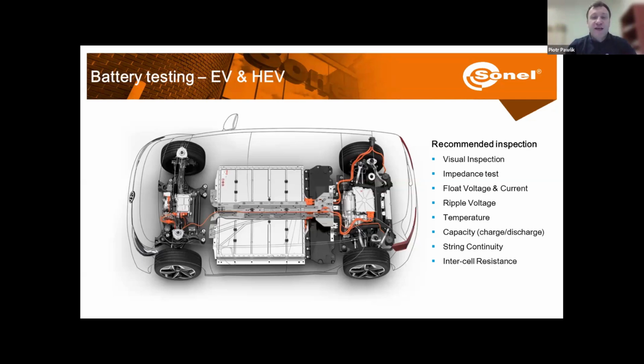But as the battery is aging, they just don't tend to keep the level of their voltages and currents. So they may fluctuate and they will have the AC component. So for that reason, we are checking impedance and not the resistance, as well as the float voltage, float current, ripple voltage, ripple current. So DC voltage and current, AC voltage and current.